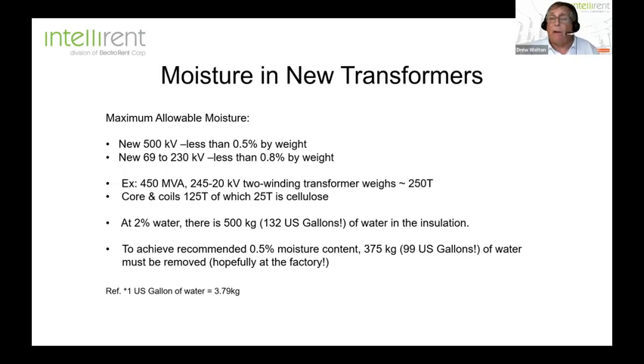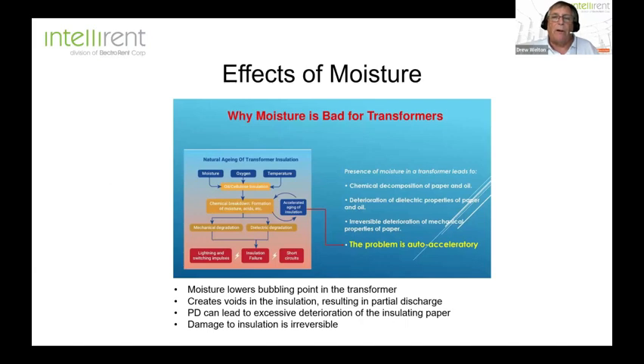They think they've got a brand new transformer, they do their routine commissioning tests, and never even look to see how much moisture might be present in that insulation from the time it leaves the factory to the time we get it put in service.